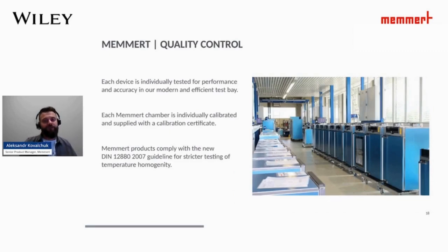undergoes individual performance and accuracy testing in our efficient test field. Every chamber is carefully calibrated and comes with its own calibration certificate. Additionally, all Memmert products comply with the latest DIN guideline, which involves stricter testing for temperature homogeneity, and reliable operations.